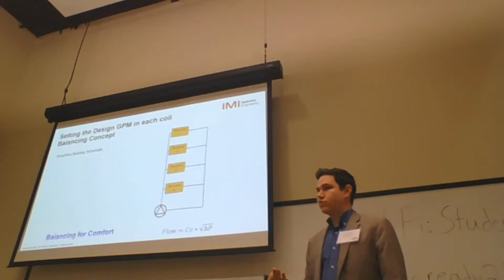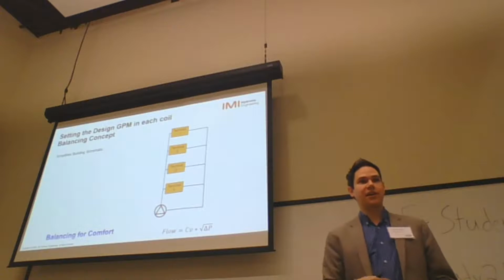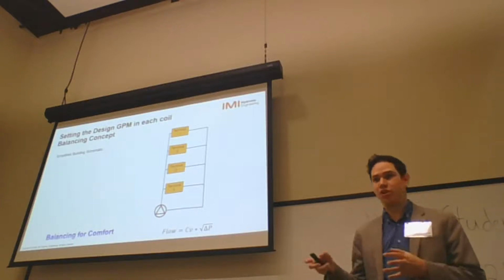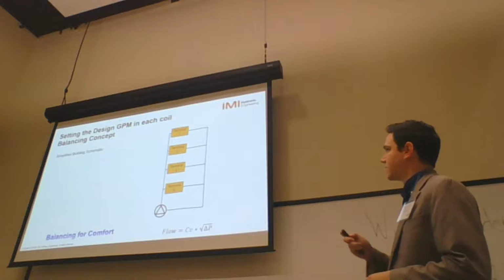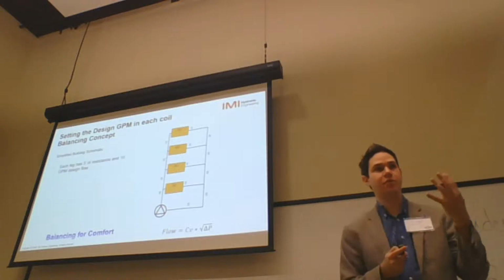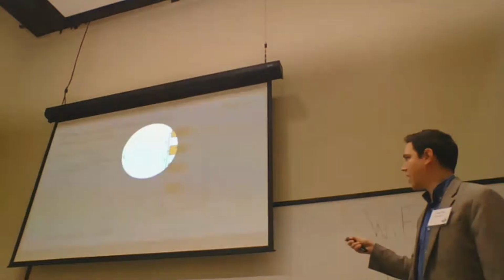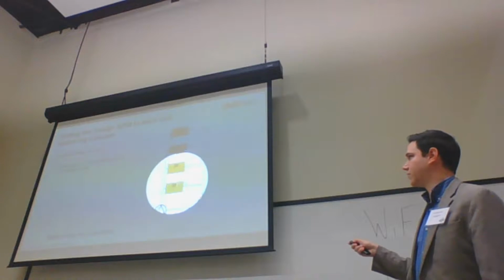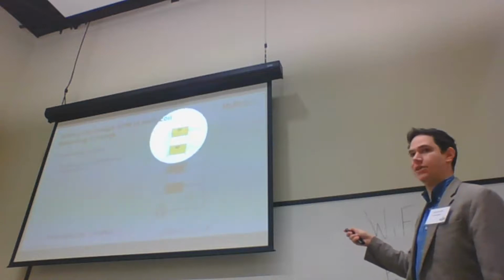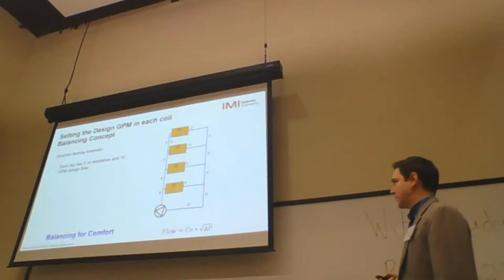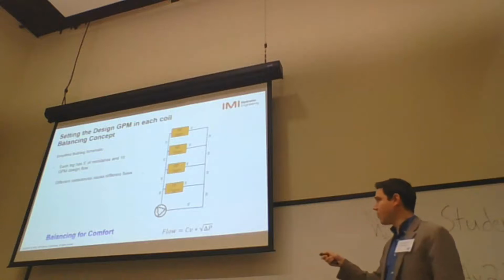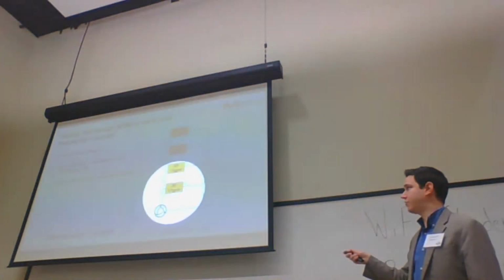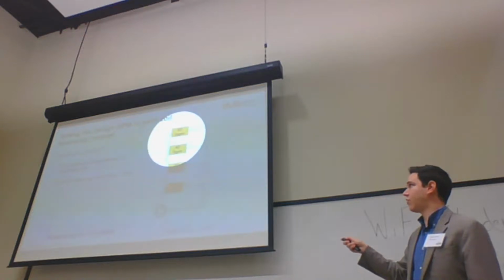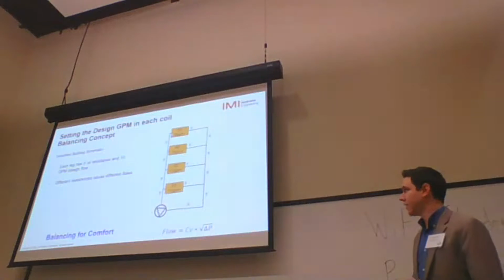So that gives us the intro to start discussing balancing and how to equalize the pressure drops in the system. I'm bringing a really simple schematic with only 4 terminal units. And for each piece of pipe right there, I have a 5 feet pressure drop. So for the pump supply water for this first coil, I need 20 to make this whole loop. And for the pump supply water for my last coil, I need 50. So with that, if I turn on my pump, I'm overflowing the first coil that was supposed to get 10 GPM, it's getting 17. And my last coil, which was supposed to get 10 GPM, is getting 3.